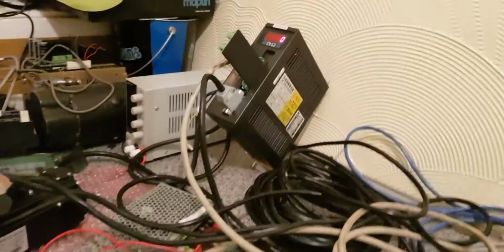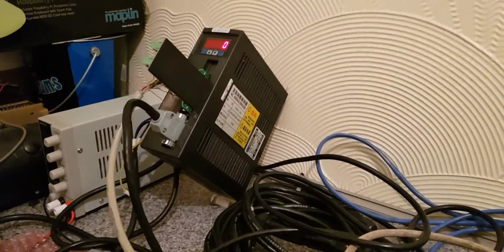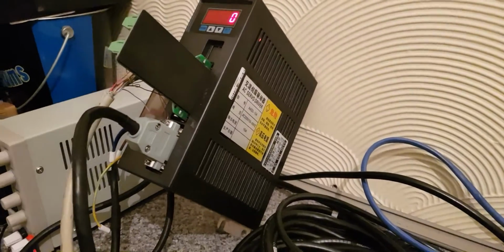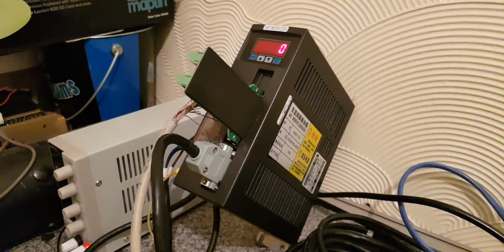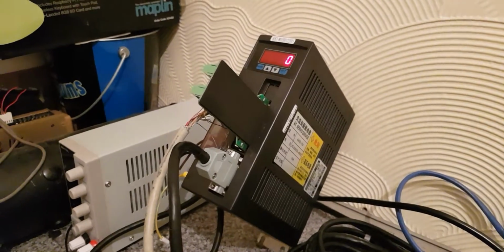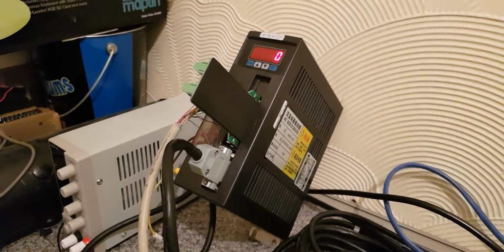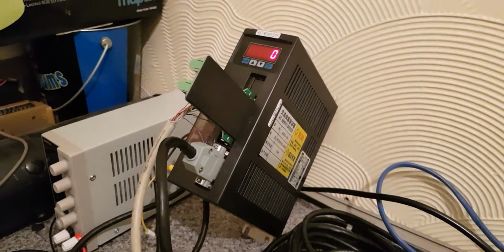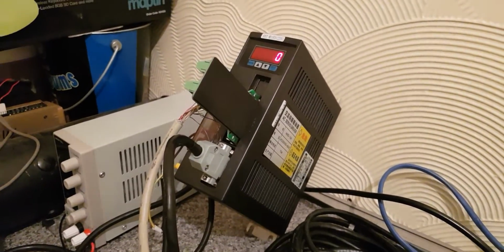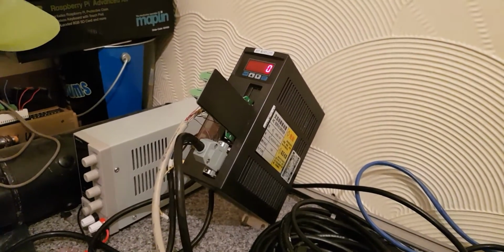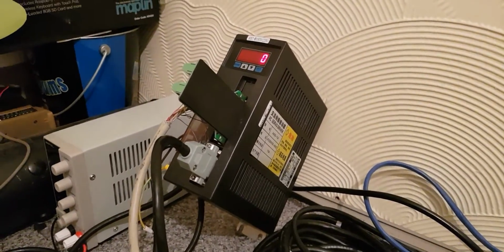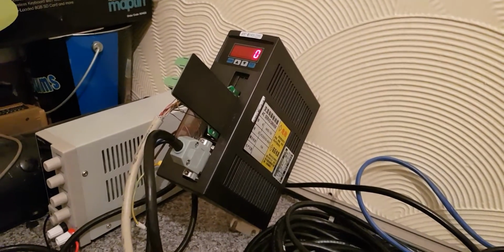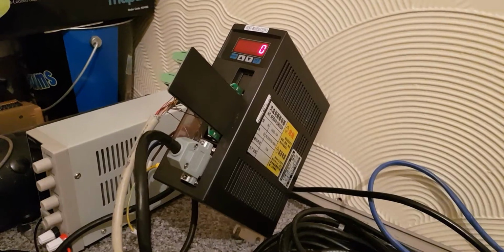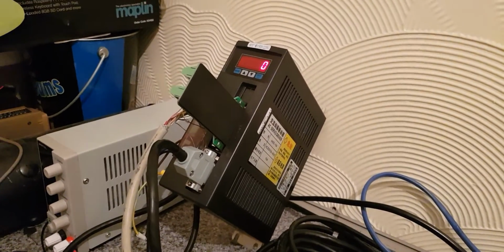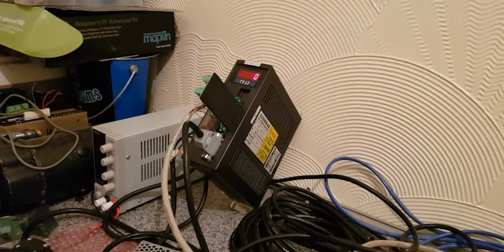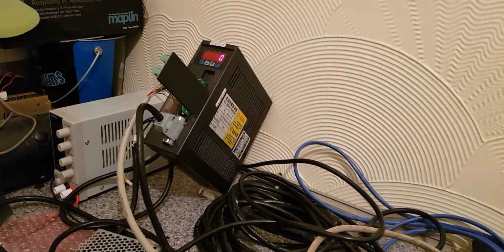So basically, how can we get more speed out of it? Well, we do it by applying what's called electronic gearing inside the drive. The drive's got the option to apply a ratio, and this is where it gets a bit confusing. It's not difficult, like anything, once you know how, but it's knowing how, because the manual is, to be honest, a good manual for a Chinese manual, but it's still very Chinglish. But in this case, where it regards this particular item in it, it's absolutely useless. So I'm going to explain it to you.